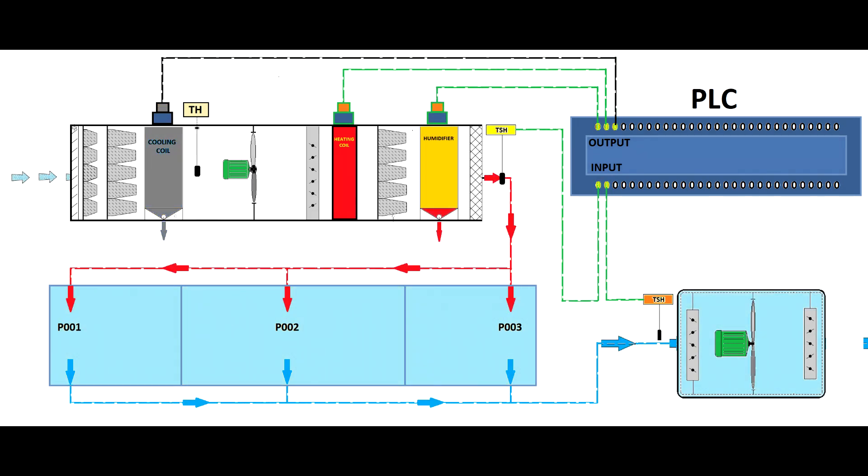Guys, now you can see I'm running the heater heat exchanger and the humidifier. You all know that if you increase the temperature, the relative humidity will show less because the heat will affect the air solubility. So please don't get confused. The absolute humidity will be increased in this case, so you keep the relative humidity constant while you're increasing the air temperature.